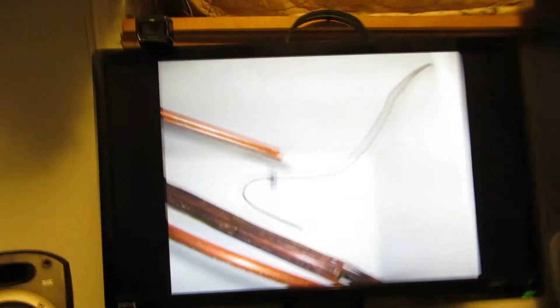So the refrigerant cools everything in here, and then the compressor actually shuts off. And as the heat from your CPU gradually warms all this fluid back up, your compressor will come back on, cool it back down, and then shut off. So the compressor doesn't have to constantly run. And if the compressor failed, it would take upwards of, say, half an hour for the CPU to warm up all this fluid in here.